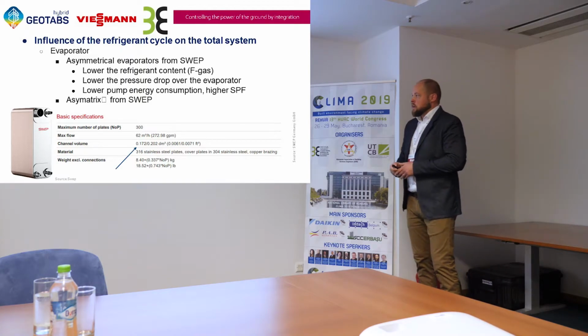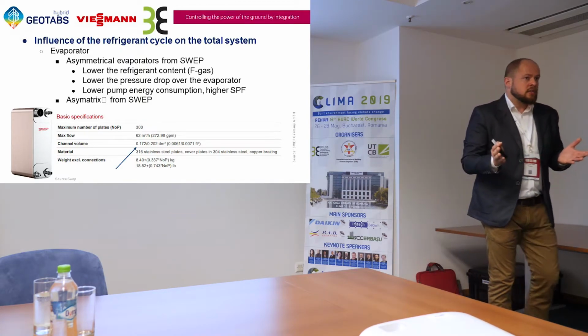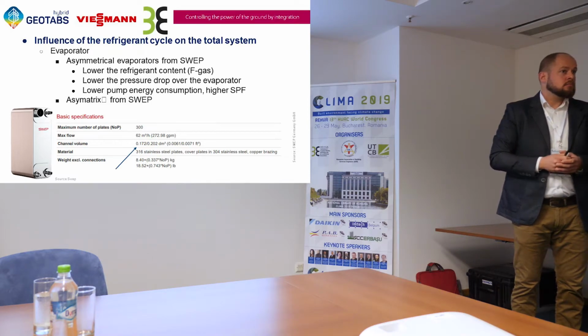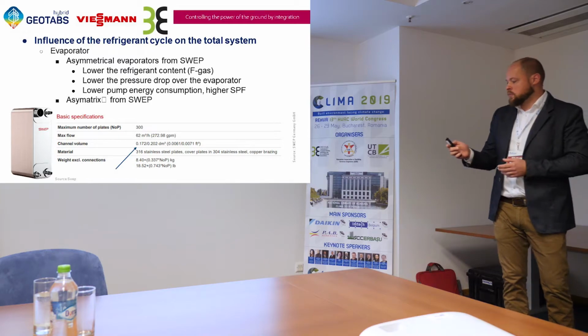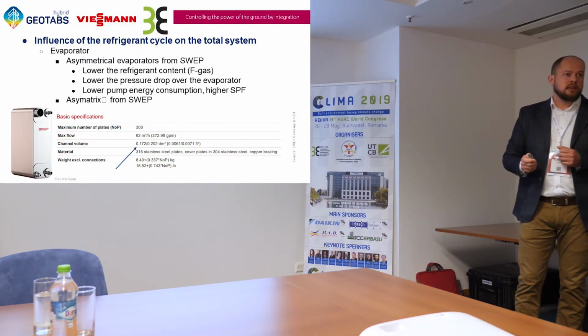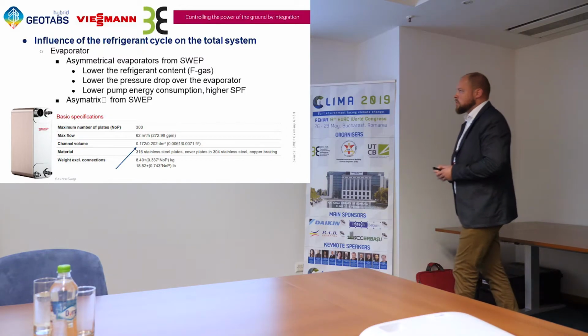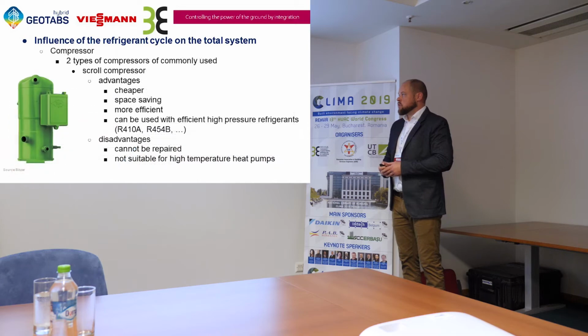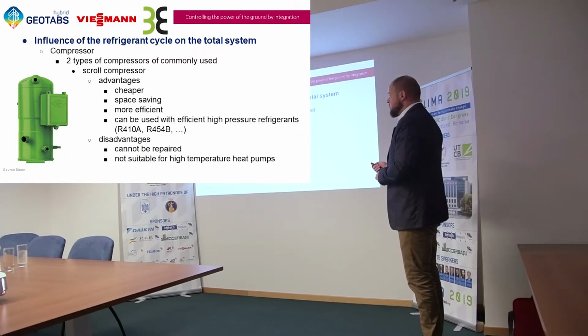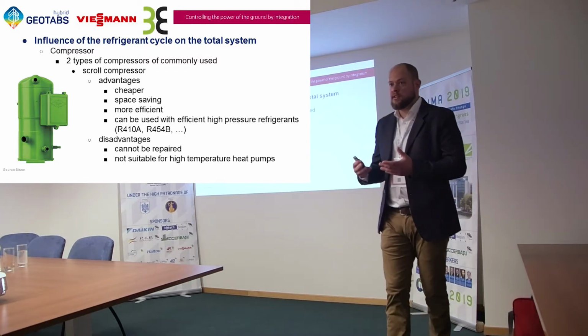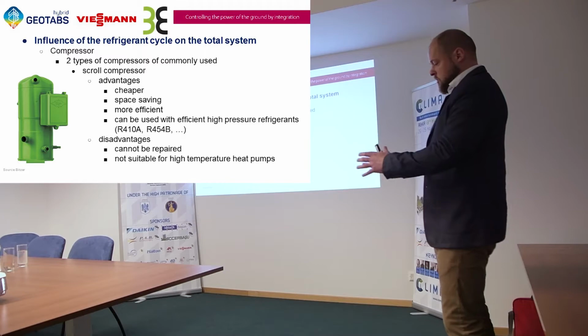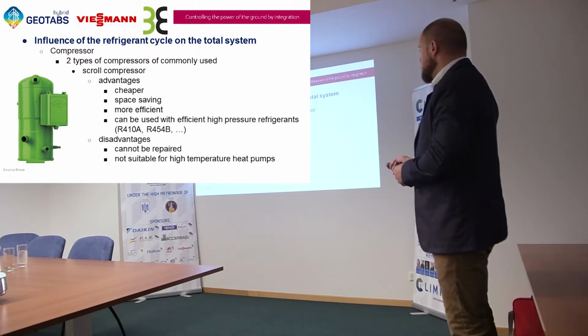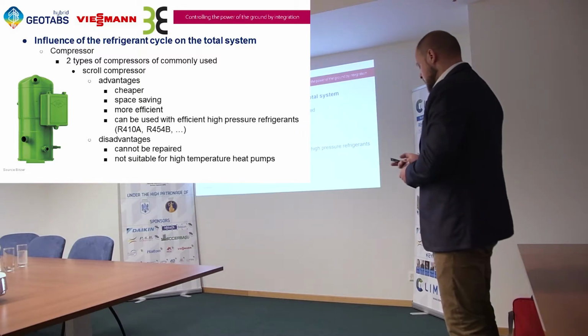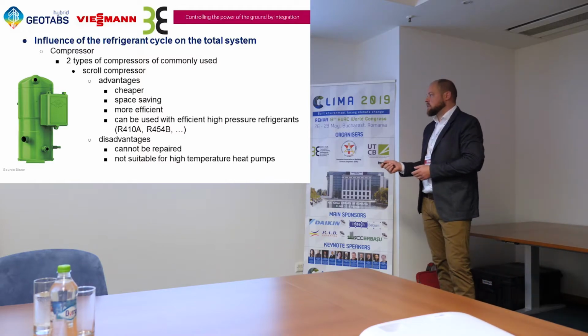Something about compressors. Which types of compressors are often used? Do you know that? Mostly we use scroll compressors, I think. And then you have an option of the reciprocating compressors with the pistons. Why do we use scroll compressors? So, two types commonly used, the reciprocating or the scroll compressor. What are the advantages of this system? It's cheaper to produce, easier to make. It is space saving because the compressor is built in the height, more efficient, and can be used with efficient high pressure refrigerants such as the R410A, which we use today, and also a newer one with a lower GWP can be used in this type of compressor.